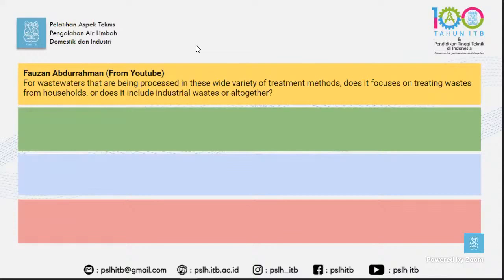Okay, so for anaerobic filters, we have many of these systems. I didn't even show them in my presentation. They are not performing well. So we could have septic tanks followed by anaerobic filters. And it's important to mention that it is different from the upflow anaerobic sludge blanket reactors I showed to you. In the UASB reactors, you do not have any packing media, okay? You just have the liquid and the anaerobic biomass, and so on. So there's no packing media. For anaerobic filters, you also have an upflow movement of the wastewater, and you have the packing media, mainly stones or gravel. When it comes to trickling filters, they are fully aerobic.